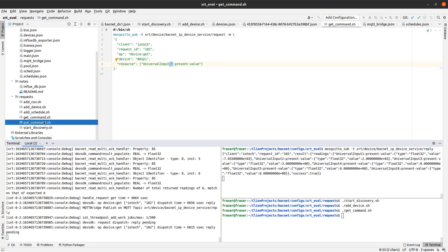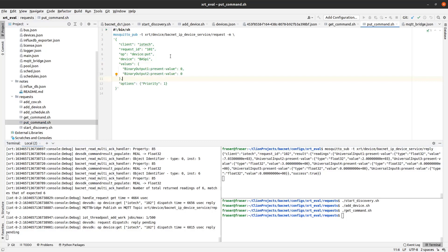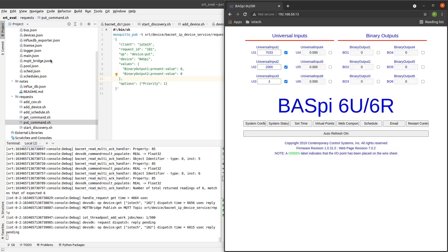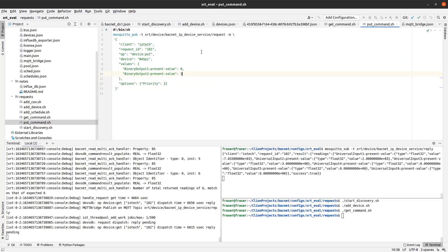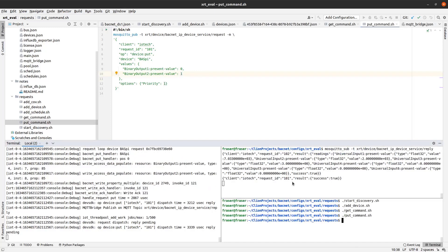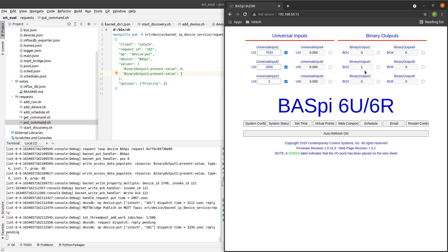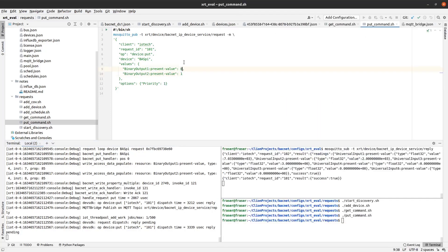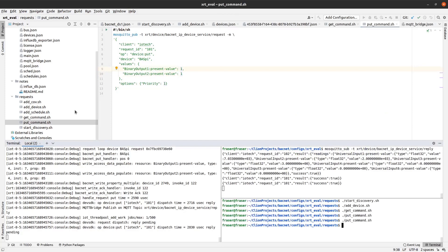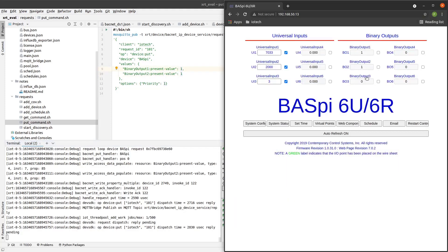The next thing that I will do is issue a PUT command to write new data values to the BACnet device. You can see the JSON payload for the PUT request. In this case, we are going to set the values of BINARY OUTPUT 1 and BINARY OUTPUT 2. You can see the current values of BINARY OUTPUT 1 and 2 using the device console client provided with the BASPi device. I will issue the request to set the value of BINARY OUTPUT 2 to 1, and you can see in the device console that this has changed. Then I will issue a request to set the value of BINARY OUTPUT 1 also to 1, and again you can see the value has now changed.